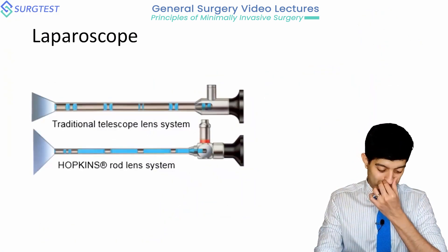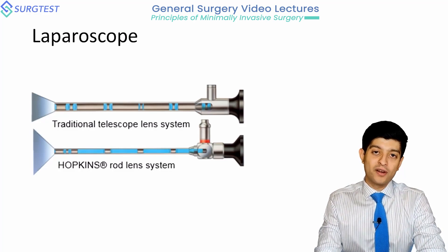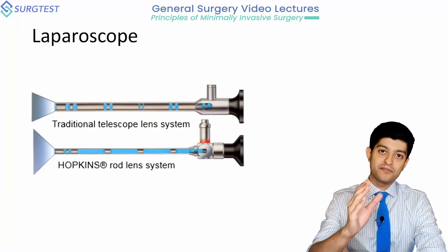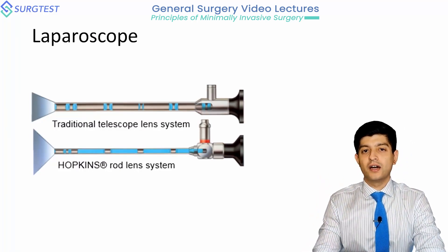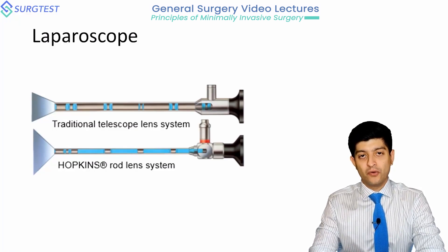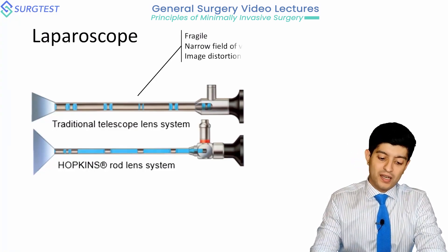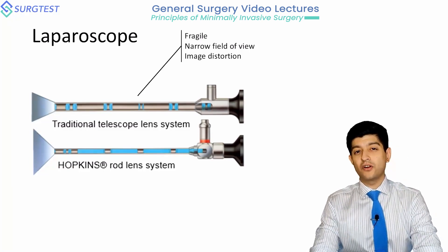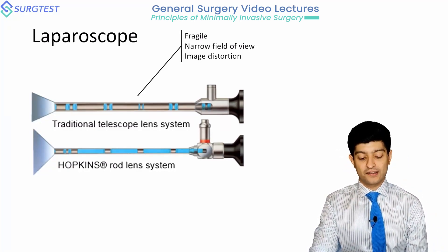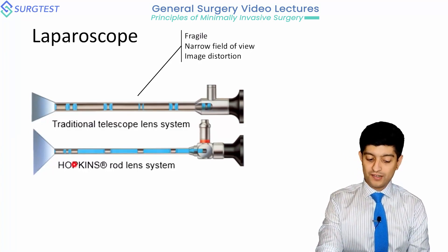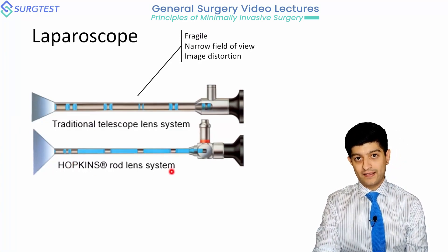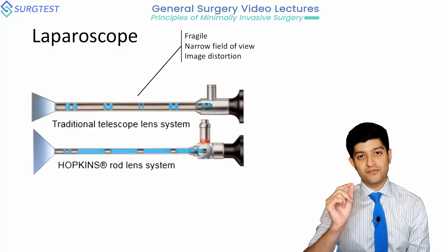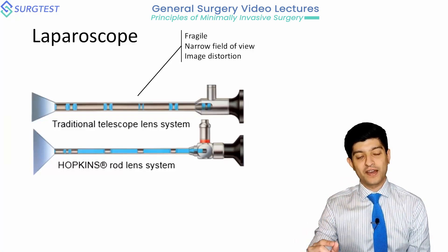Thankfully, we have camera systems now. Traditionally, laparoscopes used a lens system where several thin lenses were spaced with long intervals of air or vacuum within the scope. These were fragile, had a narrow field of view, and caused significant image distortion due to inconsistencies within the thin lenses. The system used now is the Hopkins rod lens arrangement, where long cylindrical lenses are used with very small interspersed areas of air or vacuum.